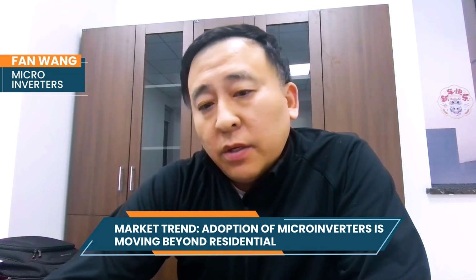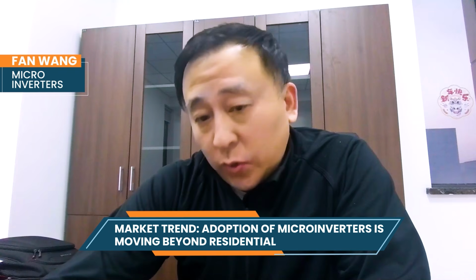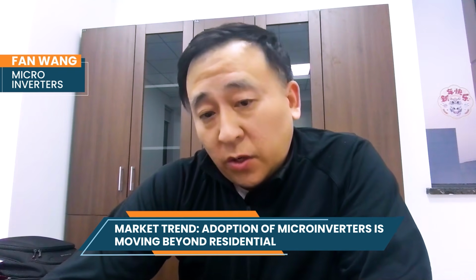Now the trend is moving beyond just residential. More and more people like to use this technology for different reasons, like safety. For the past 10 years, people needed, for example, arc fault detection because string inverters can be damaged by arc faults, since they have a high DC voltage. After 2007, starting from the US and Canada, they added a rapid shutdown requirement. Now this requirement has become mandatory not just in North America, but also in countries like Brazil or Southeast Asia.